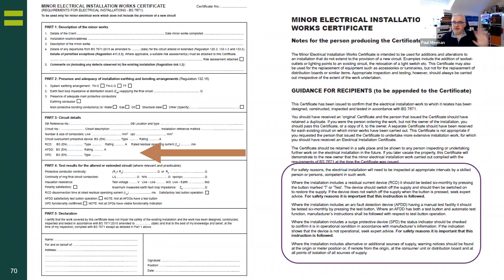Electrical installation condition report, not really massive changes on that at all, other than obviously the schedule of items inspected. But the one thing that does jump out at us is in the condition report up to 100 amps, we all know C1, unacceptable, potentially dangerous, improvement recommended, further investigation or not verified. But there's a new thing now that requires you to put an X code on the DNO equipment. Now, if you go in and it's live parts, then you would C1 it. If it's anything else, then technically the DNO equipment is outside the scope of the electrical contractor. It's property of the DNO. The relationship is between the customer in the home and the DNO.